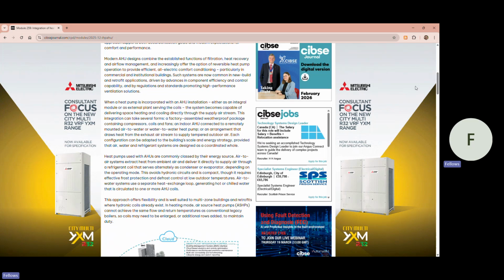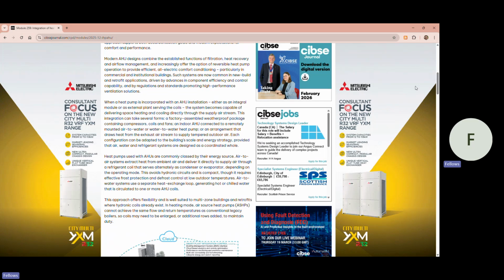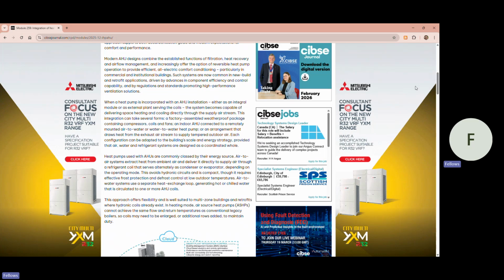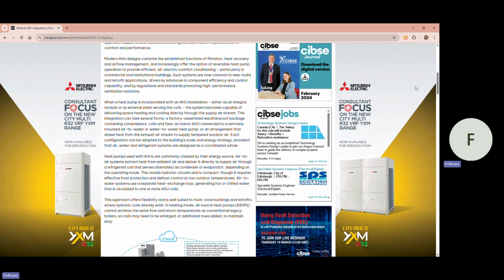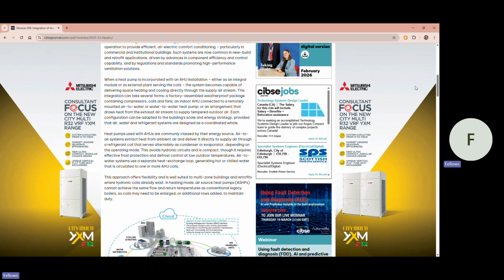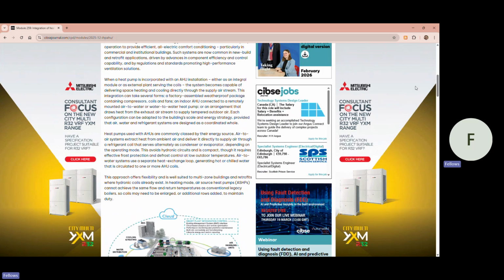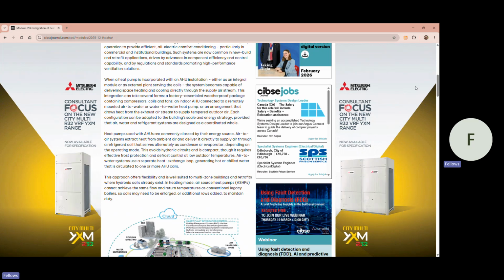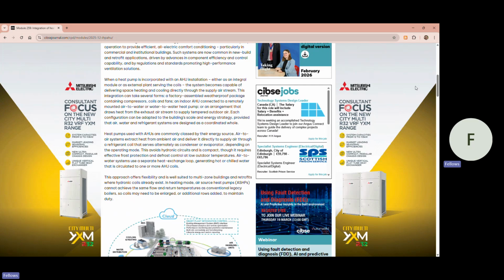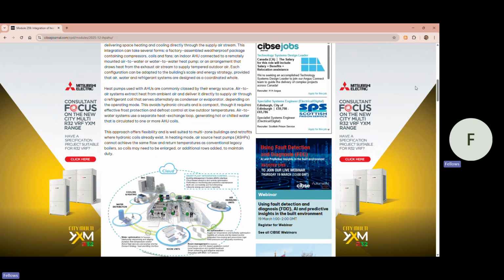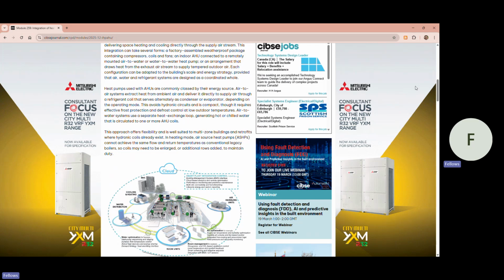Heat pumps used with AHUs are commonly classed by their energy source. Air-to-air systems extract heat from ambient air and deliver it directly to supply air through a refrigerant coil that serves alternatively as condenser or evaporator, depending on the operating mode. This avoids hydronic circuits and is compact, though it requires effective frost protection and defrost control at low outdoor temperatures. Air-to-water systems use a separate heat exchange loop, generating hot or chilled water that is circulated to one or more AHU coils. This approach offers flexibility and is well suited to multi-zone buildings and retrofits where hydronic coils already exist.